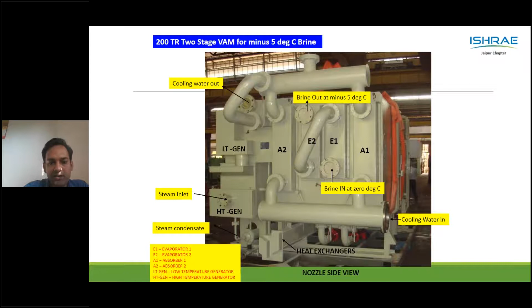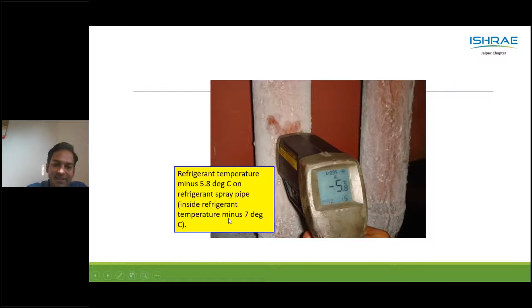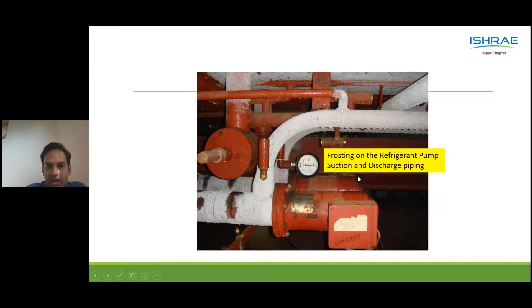This is the further classification of the two-stage -5 degree VAM with its various parts. It has 2 evaporators, 2 absorbers. This is one of the sites where we had measured -5 on the tubes, and inside the refrigerant was -7 degrees Celsius. This is the frosting on the refrigerant pump and the suction and discharge in these vapor absorption machines.